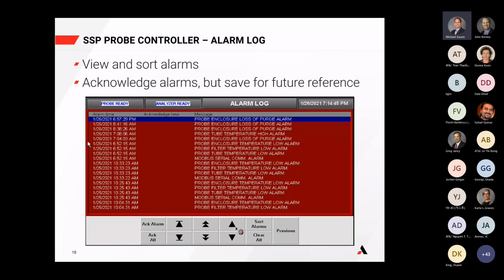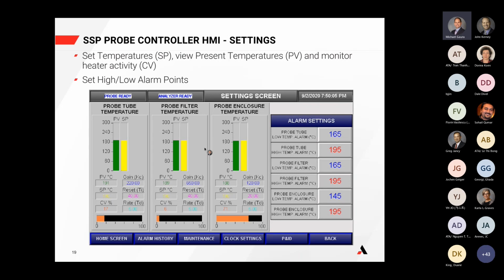They can scroll through and view alarms over time here. You can sort the alarms by time, which is what's demonstrated here, where the most recent alarms are up here, or you can sort by the way we created our alarm messages. They're detailed by location. So you could click on here and sort through and see where am I getting alarms on the probe, where am I possibly having issues with some of my communication. Those are just a couple of examples here. So again, this is the alarm log. Next screen, we're going to be looking at how we can set some of our parameters for the temperatures.